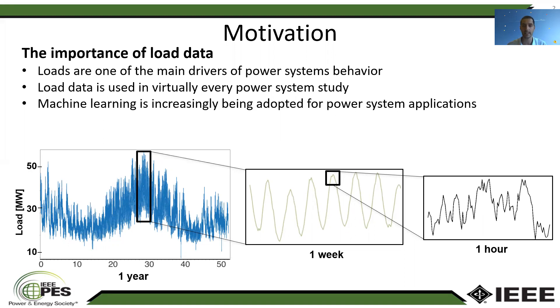It's important that we have realistic data and models to use as inputs for these studies. Time-series load data is used for almost every power system study, but the requirements in terms of sampling rate or time length vary depending on the specific study. For example, for planning we need many years ahead but at very low resolutions, whereas for dynamics or stability analysis we need just a few seconds or minutes but at much higher sampling rates. Loads show very different behaviors and patterns at different timescales, and these need to be taken into consideration depending on the study.